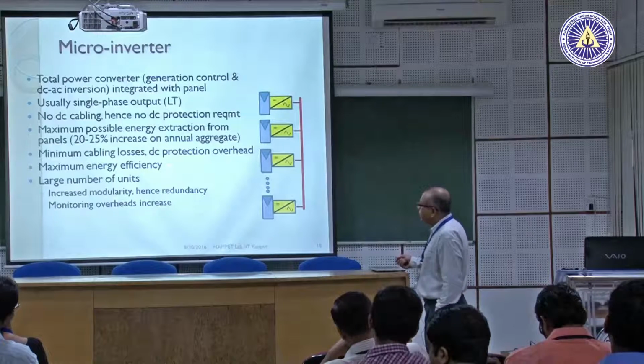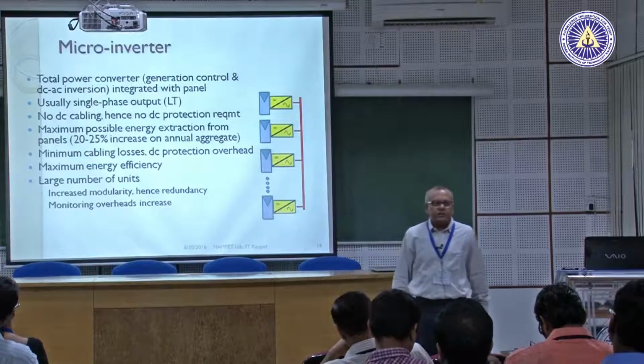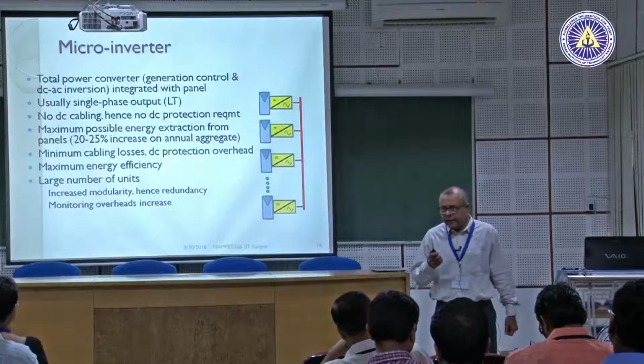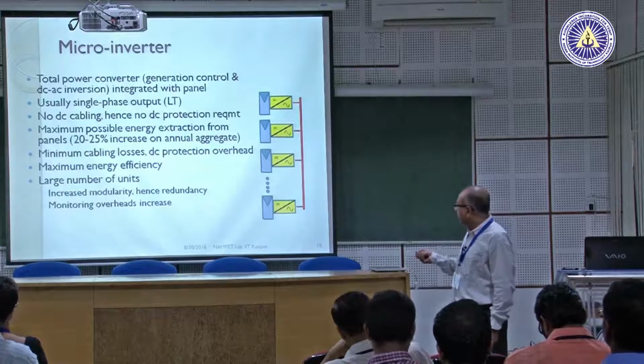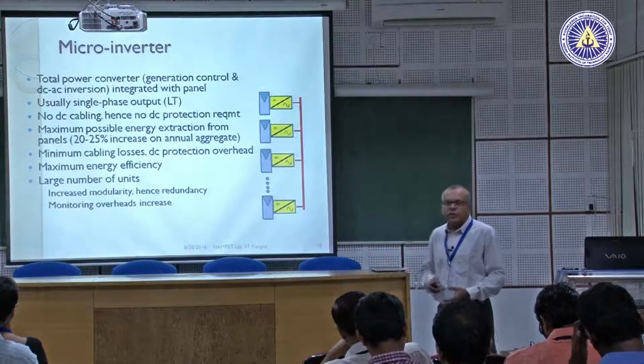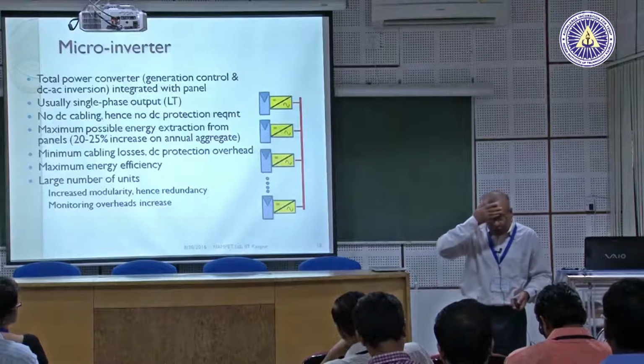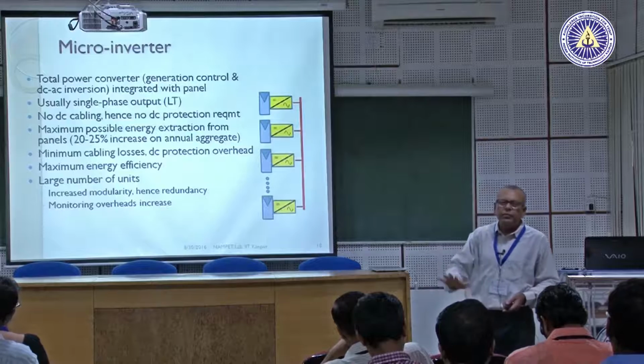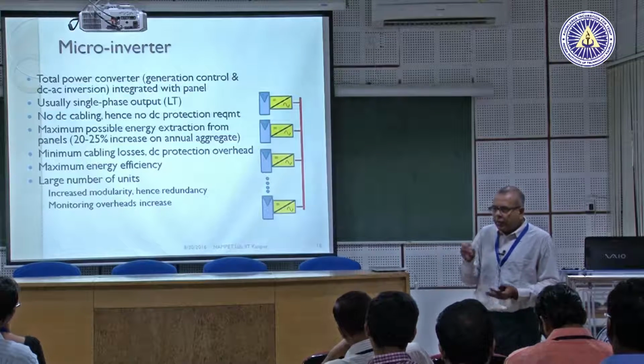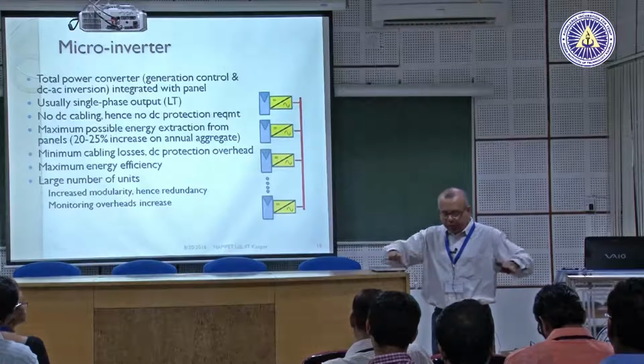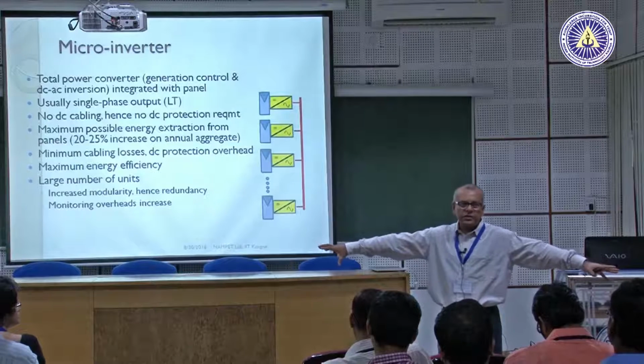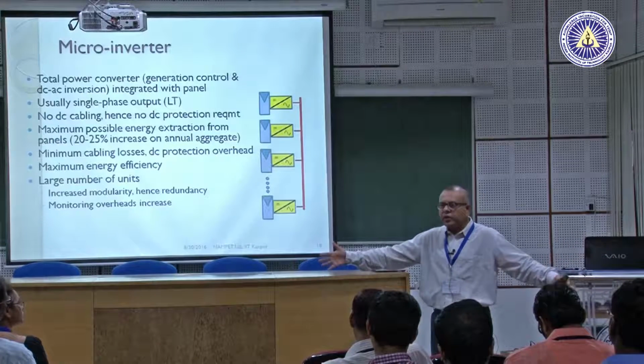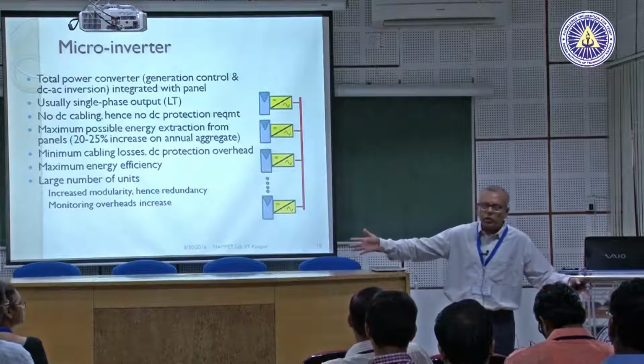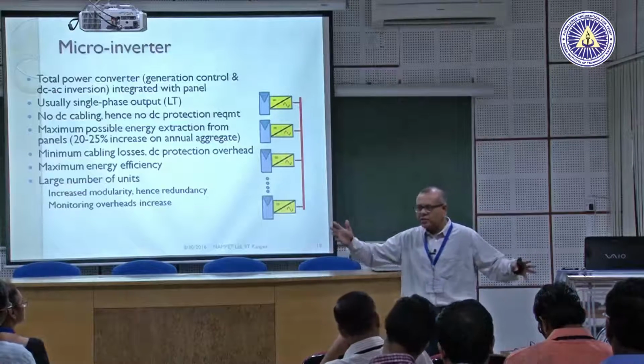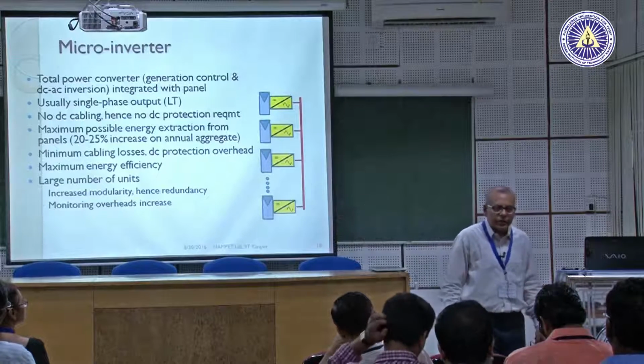The advantages are that DC cabling losses are reduced. The second advantage is that DC protection requirements are now minimal. The problem is, once I put several panels in series, the total DC voltage turns out to be at least about 400 to 600 volts. That's how typically these strings are operated.